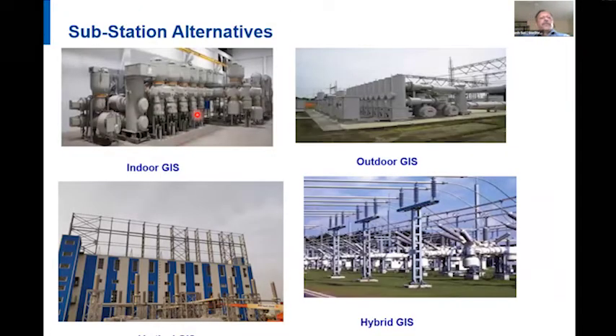This picture gives a conventional indoor GIS substation. Its disadvantage is that it involves a huge cost for the building that has to be built, along with the requirement of a crane that can carry a load of about 10 tons. In the future, if more expansion is needed and there's no space in the building, another PEB building has to be built next to it, increasing the cost of expansion.